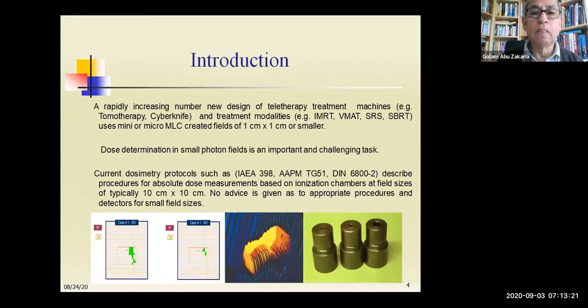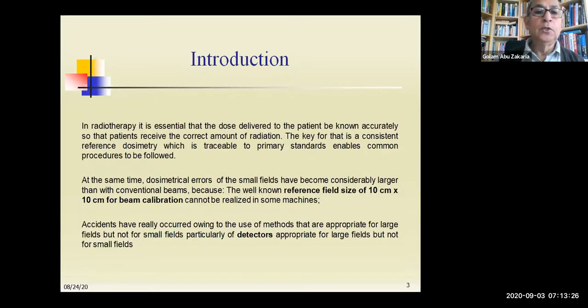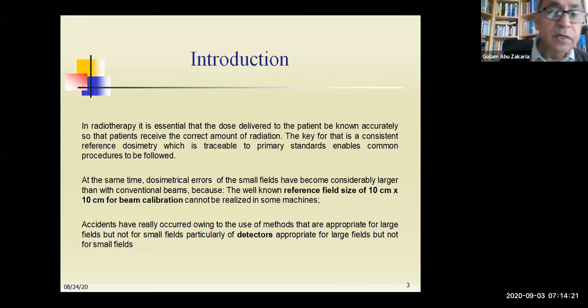So everybody knows that in radiotherapy we should determine the dose very accurately, which is also important. The key point is consistent reference dosimetry, which is traceable to a primary standard. This is very important. At the same time, the dosimetric error in small field dosimetry is higher than in conventional dosimetry. The conventional dosimetry is designed for a reference field size of 10 by 10 centimeters at 10 centimeter depth, with a calibration coefficient from a standard primary laboratory. Some people used this protocol for small field dosimetry. Therefore, massive mistakes, and in some cases, it resulted in accidents.